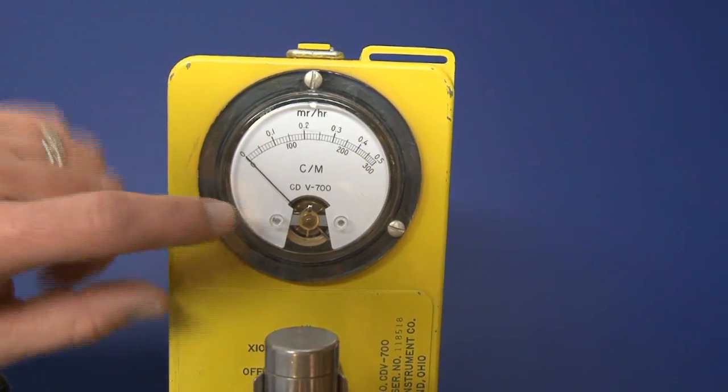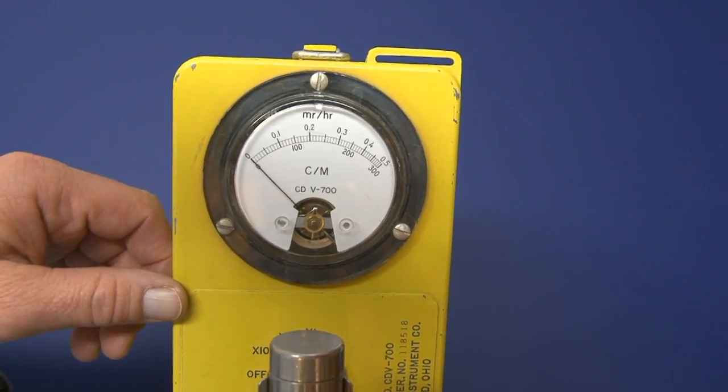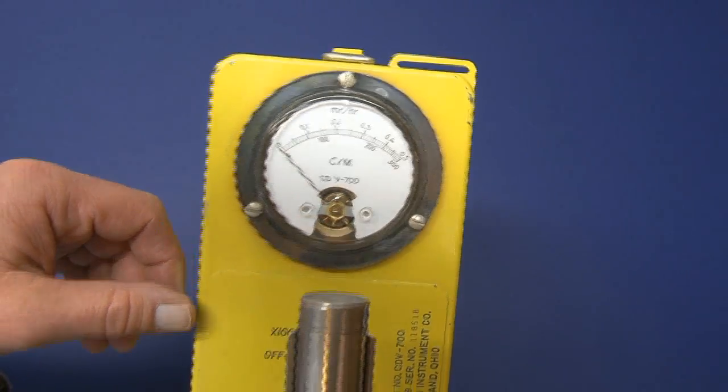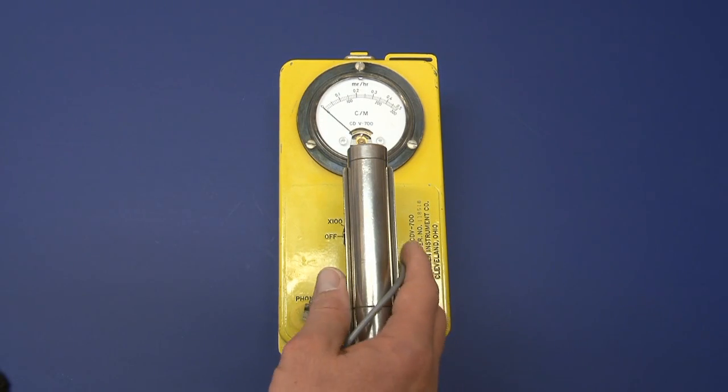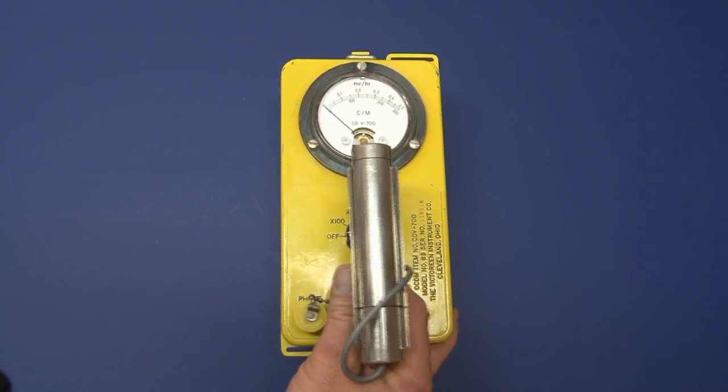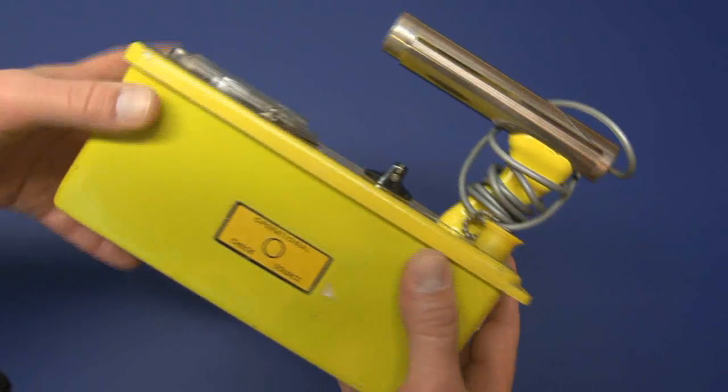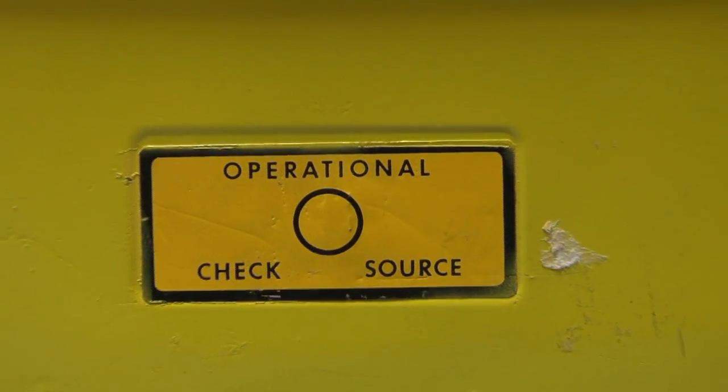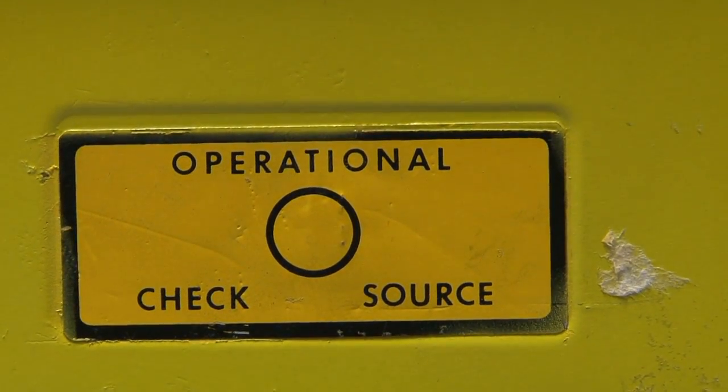Now before we use this instrument one of the things we want to do is we want to perform an operations check or a source check. These instruments usually have an operational check source on the side.